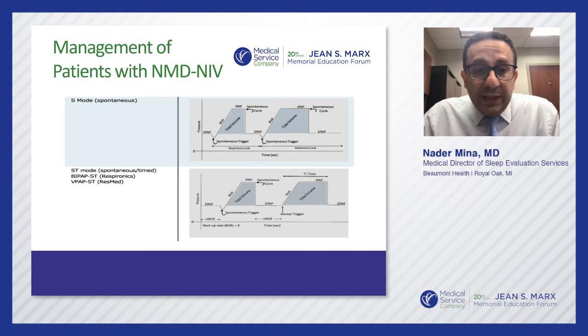Versus the ST mode, which has a dual function. In the second graph, if you look at the first curve, if the patient triggers the breath, then the patient decides when to cycle from IPAP to EPAP, which means how long the inspiratory time is. However, if the device delivers a timed breath, then the device determines the inspiratory time and cycles depending on the cycling settings that we put. So again, in the first mode, the patient determines the inspiratory time. In the second mode, the patient determines when they initiate the breath, but if you deliver a breath through the device, then the device determines the time.